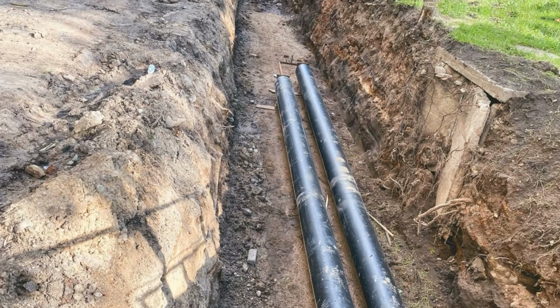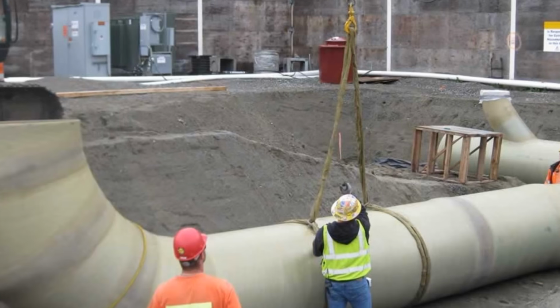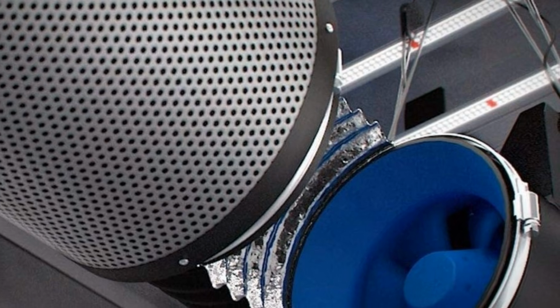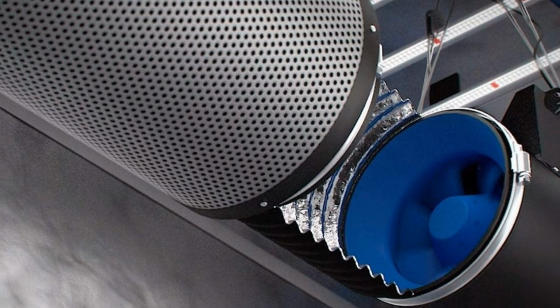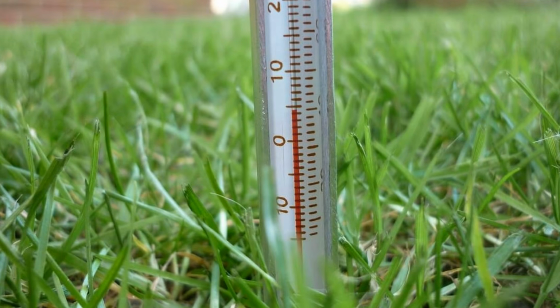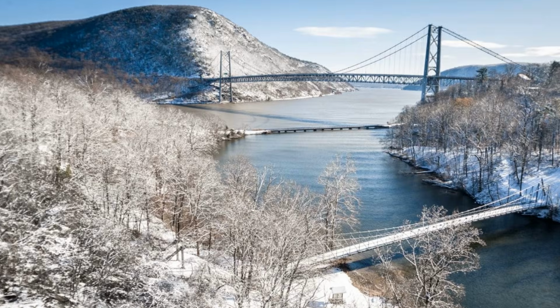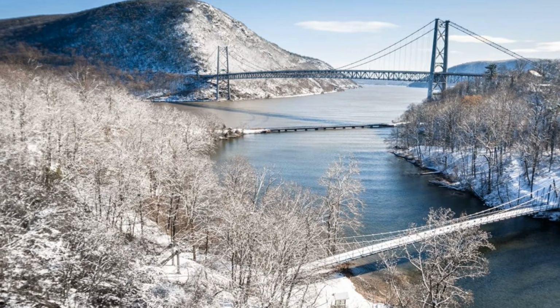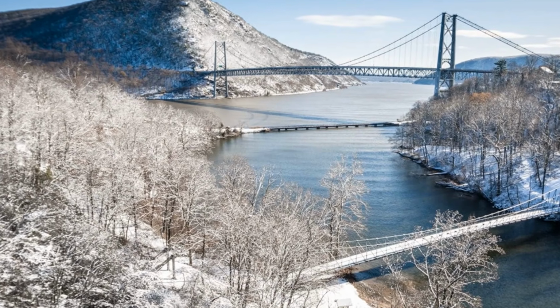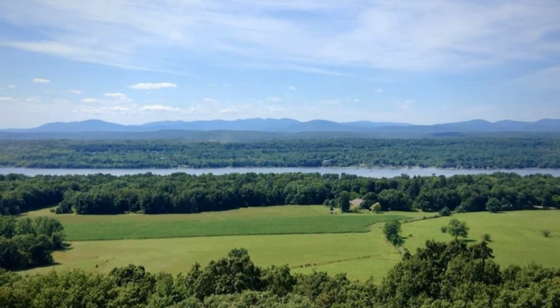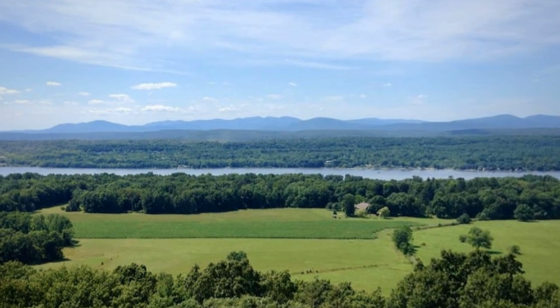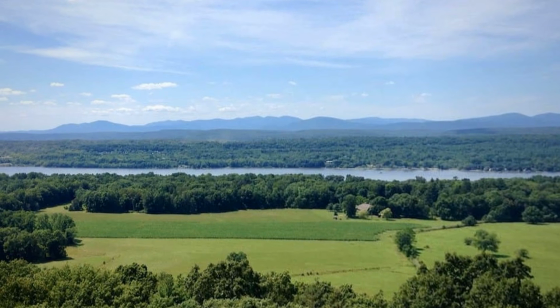It is 12 pipes buried 5 feet underground, each one 100 feet long. Air pulled through those pipes arrives at the building between 52 and 58 degrees Fahrenheit. Every month, every season. January in the Hudson Valley, when the air outside is 14 degrees Fahrenheit. August in the Hudson Valley, when the air outside is 94 degrees Fahrenheit. The ground does not care.